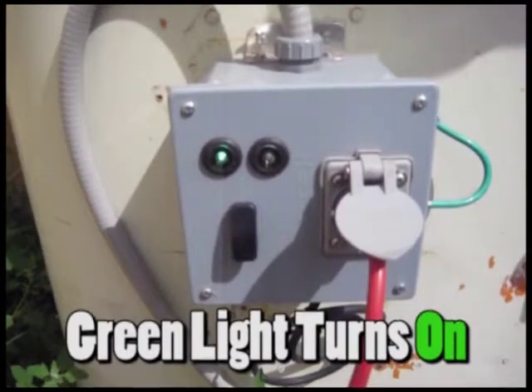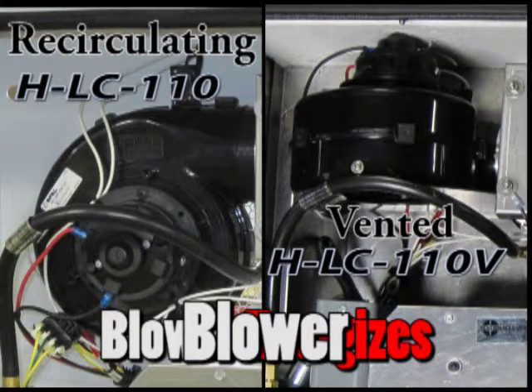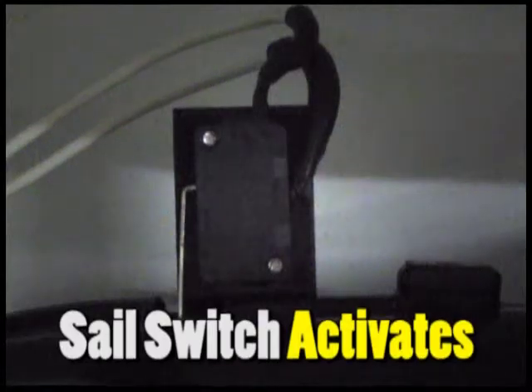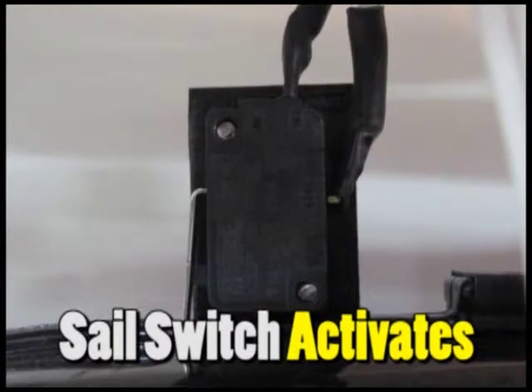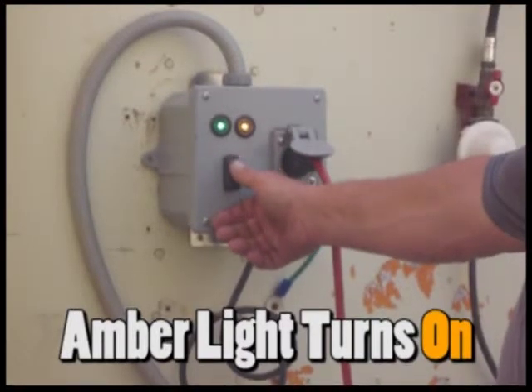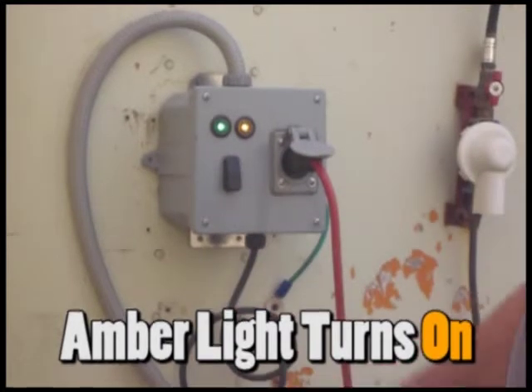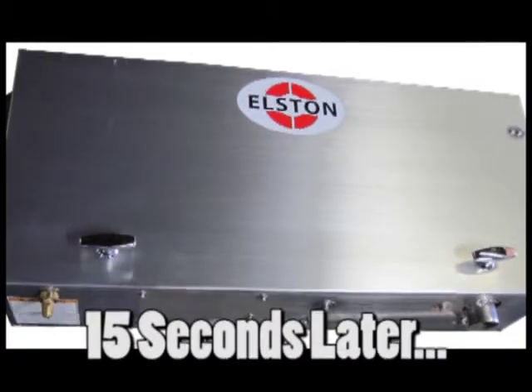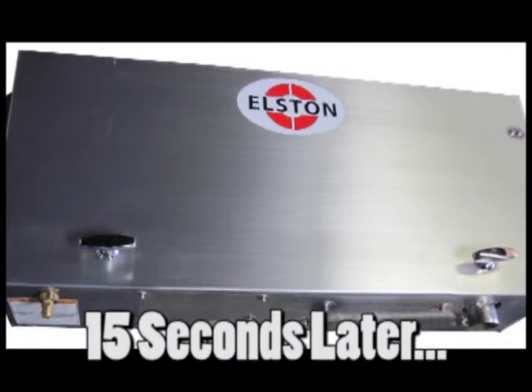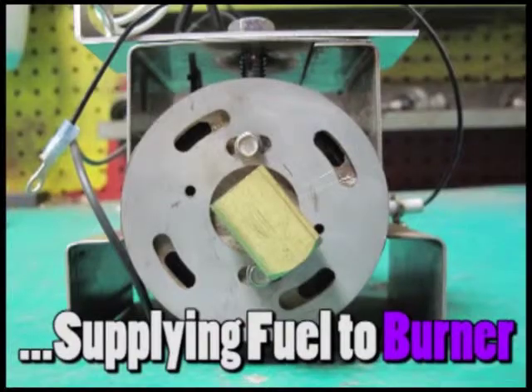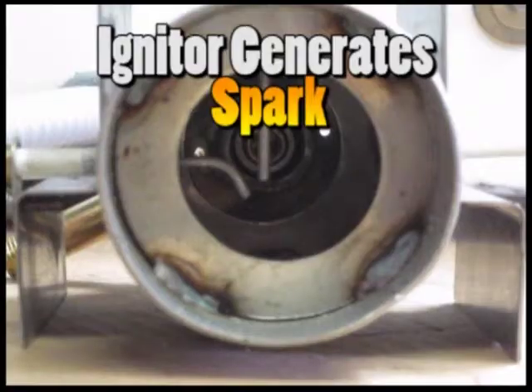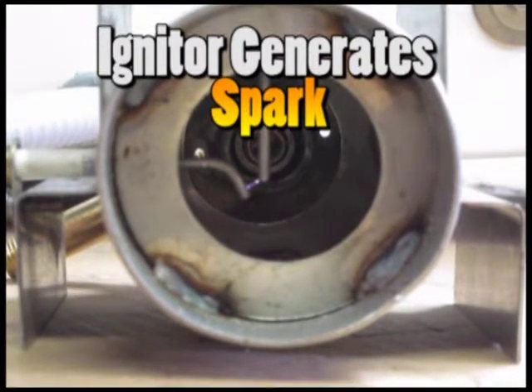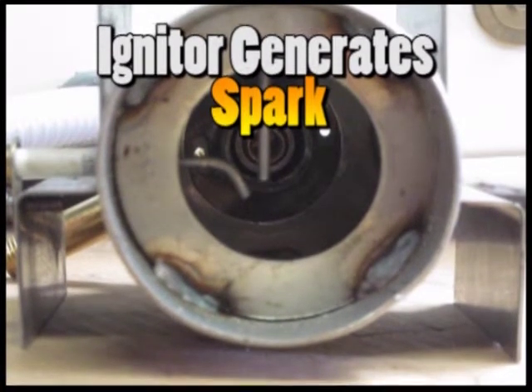The green light will come on and the blower will energize. As the blower energizes, it activates a snap action switch. This sail switch is used as an automatic safety device that will detect if the blower is malfunctioning or underperforming. After the switch activates, the amber light will come on to signal the start of the ignition process. Approximately 15 seconds after the amber light activates, the gas valve will open, supplying fuel to the burner, and the igniter will generate a spark for approximately 7 seconds, attempting to ignite the fuel.